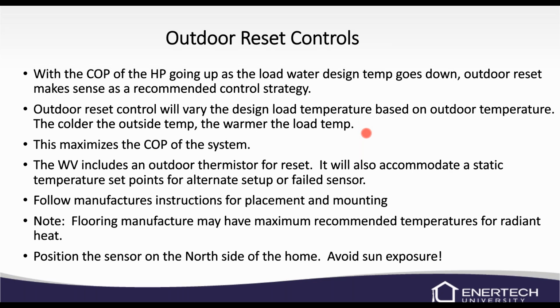Outdoor reset. So outdoor reset, that's why we send the outdoor temperature sensor. Obviously, the COP, or the efficiency of the heat pump, will go up as the load water design goes down. So the outdoor reset does make a lot of sense here. It's going to vary the design load temperature based on the outdoor temperature. So the colder the outdoor temperature, the warmer the load temperature. It's going to maximize the COP of the system.